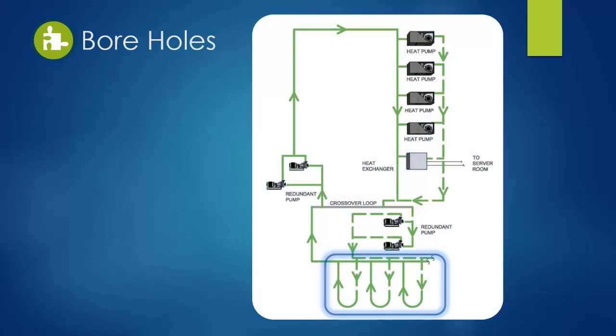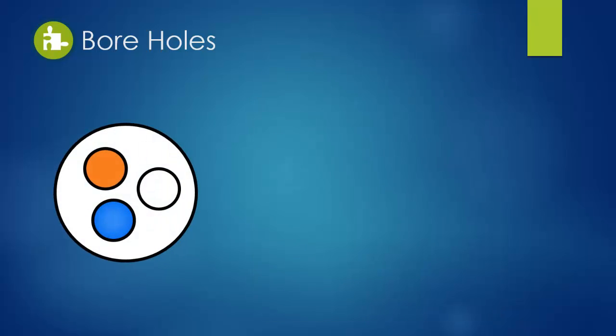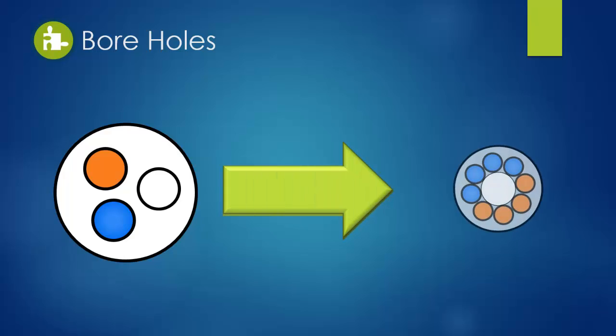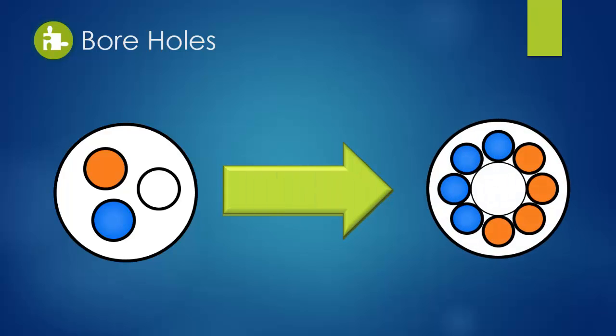Component 1 is the boreholes. Boreholes are composed of piping which uses the ground as a heat sink or heat source depending upon the outside temperature. To maximize heat transfer in the boreholes, a twister borehole technology will be used. A standard ground source borehole requires 3 pipes, 2 that are connected in a U-bend to allow water to flow between them, and 1 that is left open at the bottom to grout the space between the piping and the earth. The twister borehole uses the same area as one traditional borehole, but wraps 8 3/4-inch pipes around a 2-inch center core to create 4 loops.